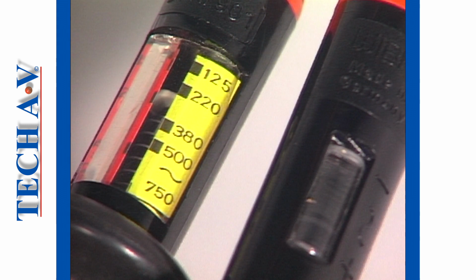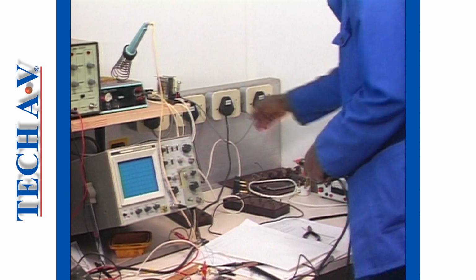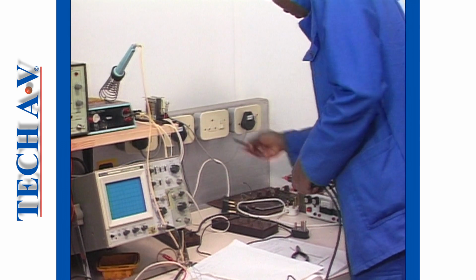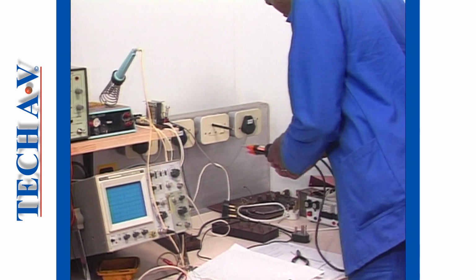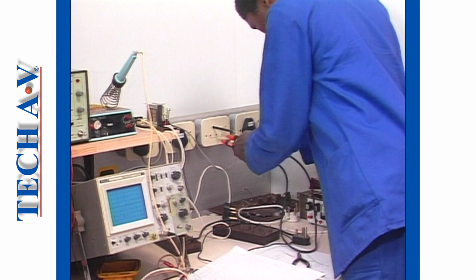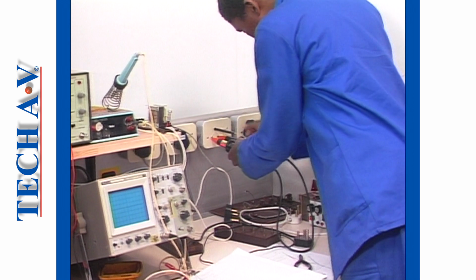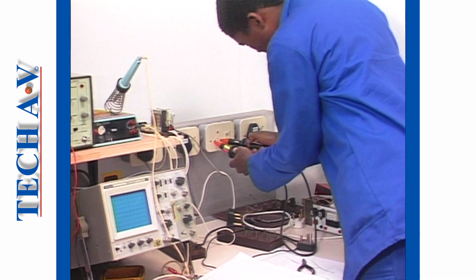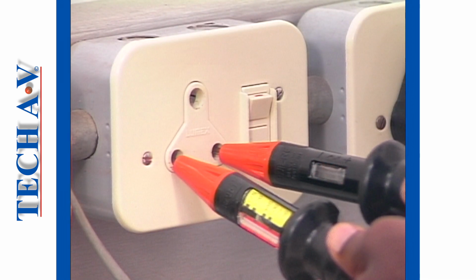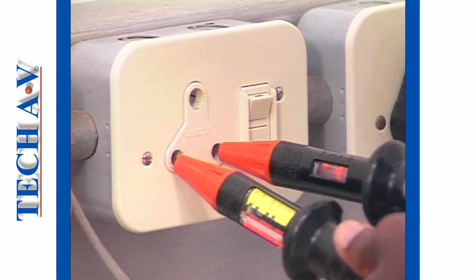Do not assume that a socket is dead if the neon indicator does not light up. What you should do in this case is take your probe tester to a socket that is known to be working. Using this socket, check that the indicator light is actually functioning. In other words, test your tester before condemning a power point.